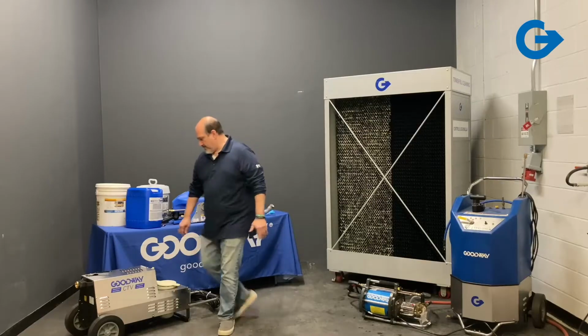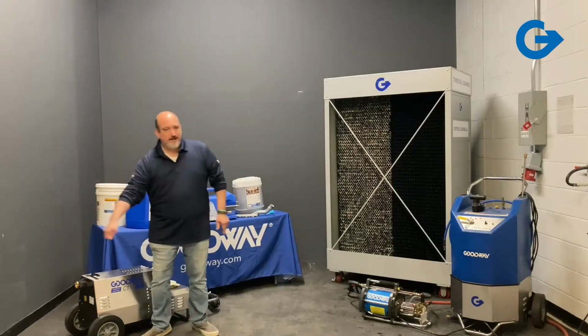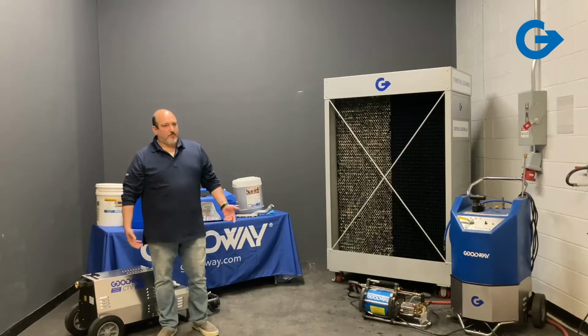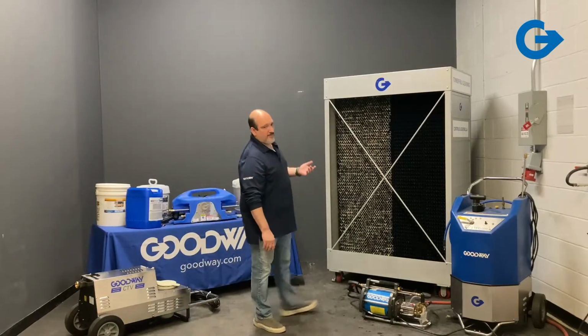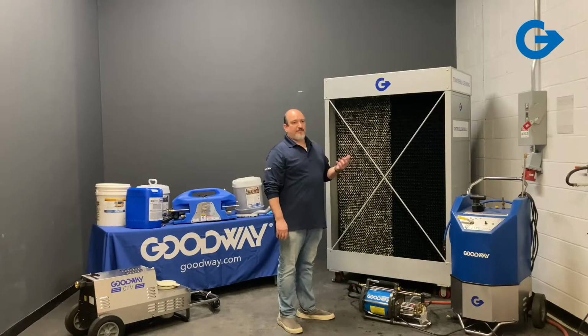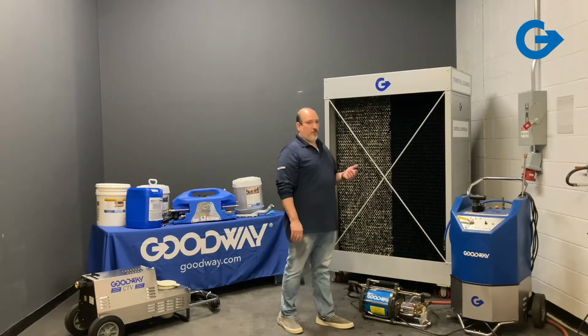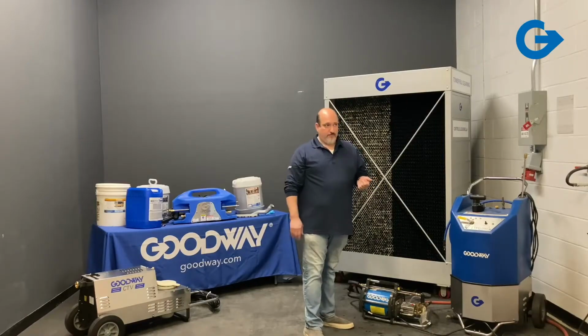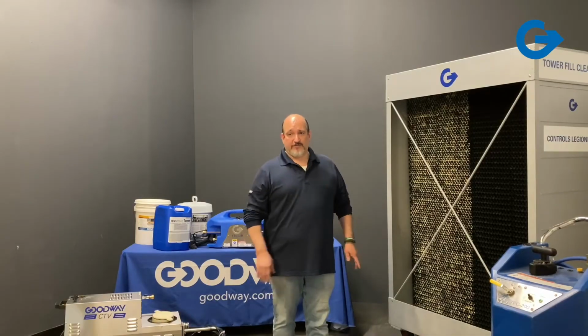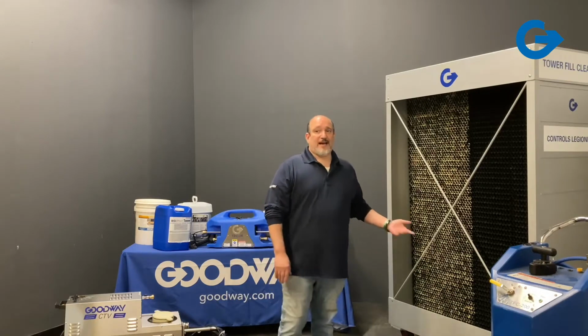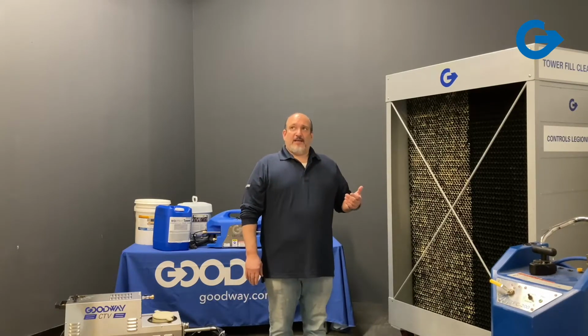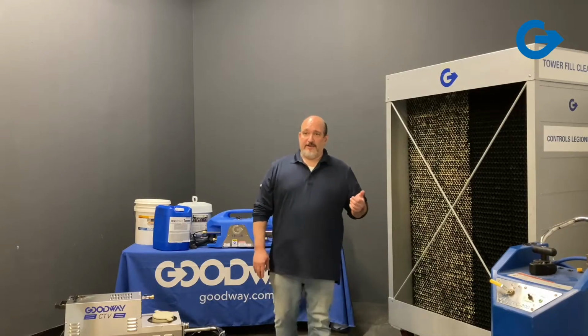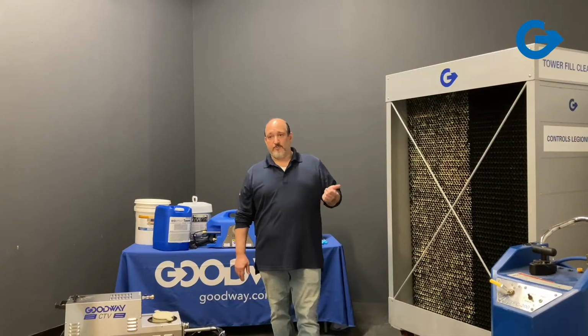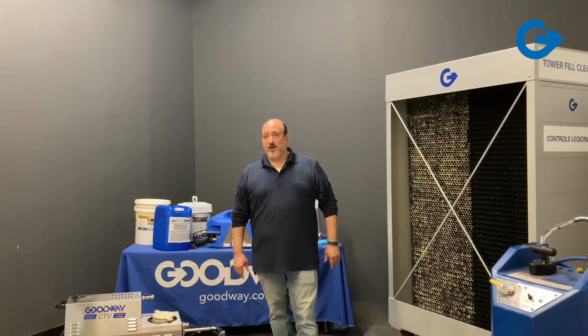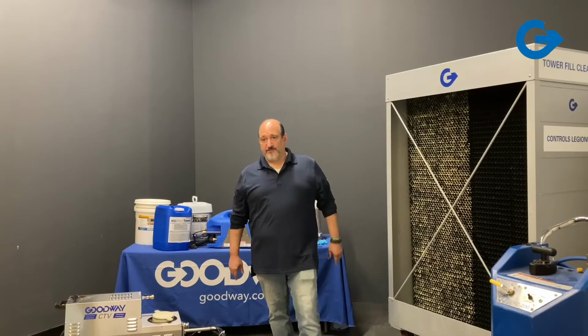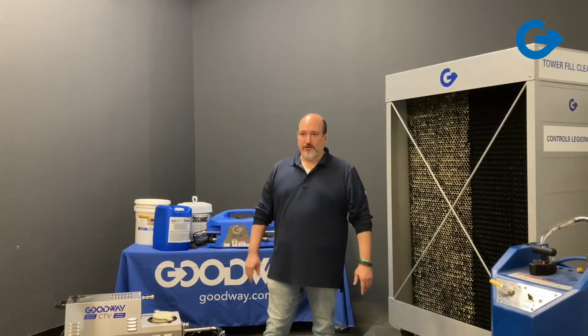So you've got your discharge going to your roof drain, and it's a pretty simple process. But what we see is there are some places where even losing 5 or 10% of your water is too much. It's more than what they want to go through. And they'll use it for vacuuming out the tower, and in a couple hours' time, you've got all that mud and that sediment out of your tower. And what's nice is that you also see a pretty immediate difference in your temperature and your pressure when you're monitoring your system, because you've just taken out maybe 100 gallons worth of mud out of your system that would be hurting the heat transfer in your chillers.